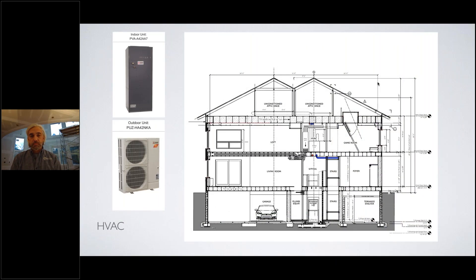For heating and cooling we're using a mini-split system, very popular for many passive houses. Originally we had two smaller units, one for each floor, but we noticed the static pressure was a little limiting. For peace of mind we changed to a single downflow unit with a more powerful fan, which also allowed us to combine the first and second floor ductwork. All the ductwork now runs within the second floor assembly or in a soffit in the hallway.